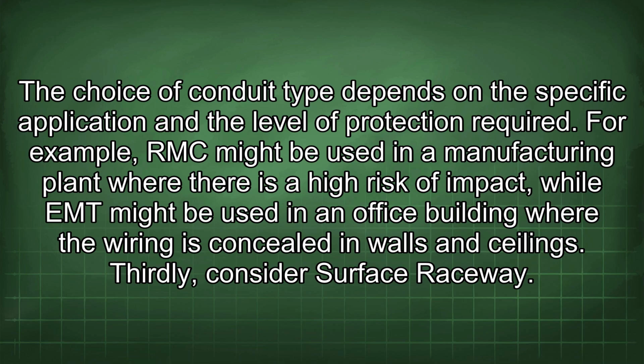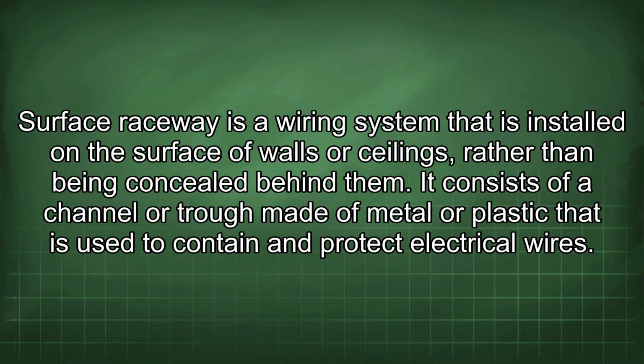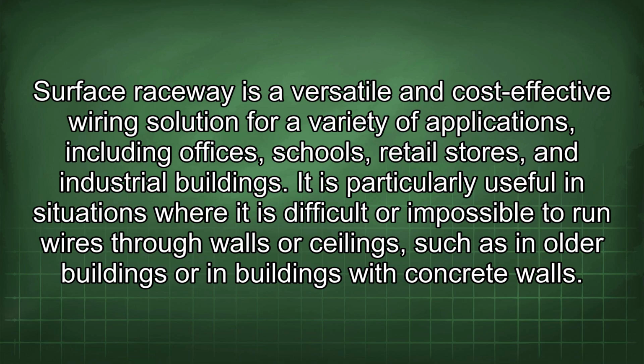Thirdly, consider surface raceway. Surface raceway is a wiring system that is installed on the surface of walls or ceilings, rather than being concealed behind them. It consists of a channel or trough made of metal or plastic that is used to contain and protect electrical wires. Surface raceway is a versatile and cost-effective wiring solution for a variety of applications, including offices, schools, retail stores, and industrial buildings. It is particularly useful in situations where it is difficult or impossible to run wires through walls or ceilings, such as in older buildings or in buildings with concrete walls.